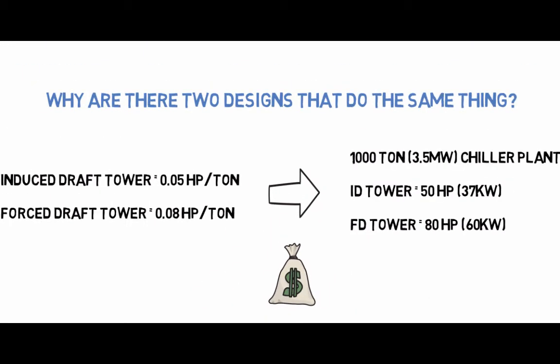With the compelling monetary incentives to use an induced draft tower, when would someone select a forced draft tower? They can be easier to maintain, they typically last longer since the fan components are not within the path of the saturated discharge air, and sometimes they can save space. So depending on the site requirements and climate, one design usually makes more sense to use over another.